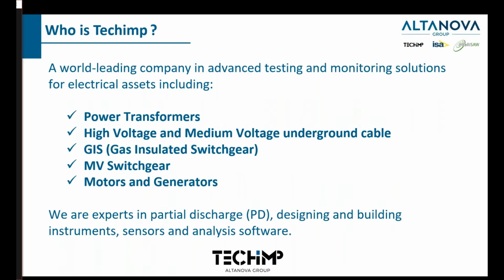As I mentioned, Techimp is a leading company in advanced testing and monitoring solutions. We cover almost all the power apparatus, medium voltage to high voltage, including the transformers, the cables from both medium voltage and high voltage, GIS, medium and high voltage switchgears, and motors and generators. As I mentioned, we are the experts in PD testing. We design and manufacture all the equipment and the sensors that we use for our testing services and also monitoring solutions.